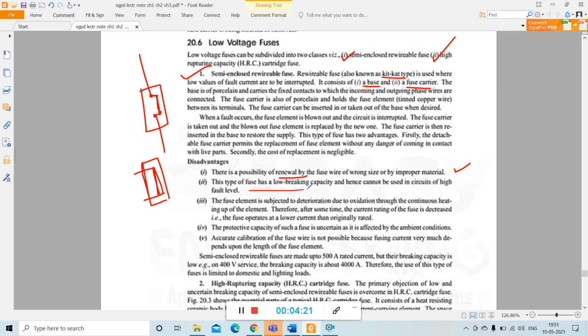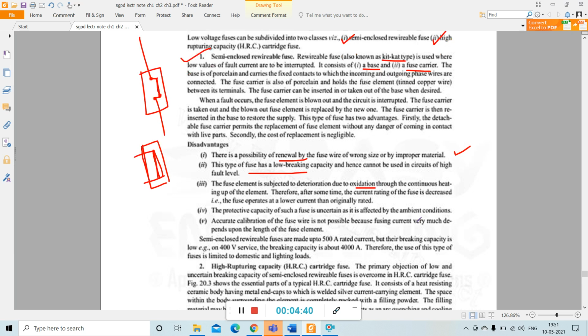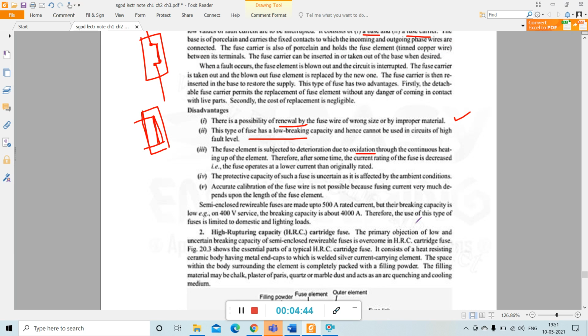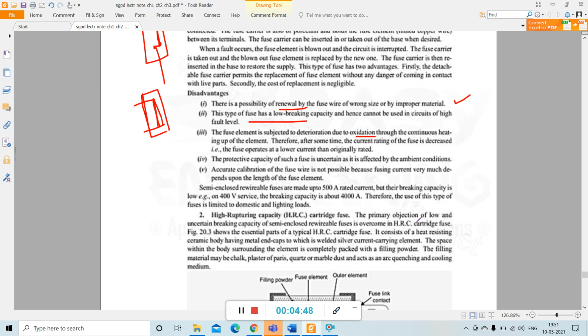This type of fuse has low breaking capacity and hence cannot be used in circuits of high fault level. The fuse element is subjected to deterioration due to oxidation through the continuous heating of the element. Therefore, after some time, the current rating of the fuse is decreased. That means the fuse operates at a lower current than originally rated. Clear? The protective capacity of such a fuse is uncertain as it is affected by the ambient condition. Accurate calibration of the fuse wire is not possible because the fusing current very much depends upon the length of the fuse element. This type of fuse is made up to 500 ampere rated current, but their breaking capacity is low. That means on a 400 volt service the breaking capacity is about 4000 ampere. Therefore this type of fuse is limited to domestic and lighting loads.